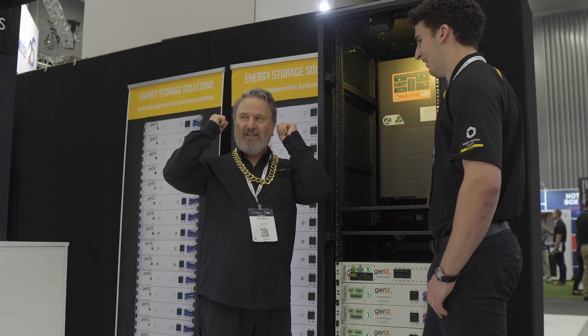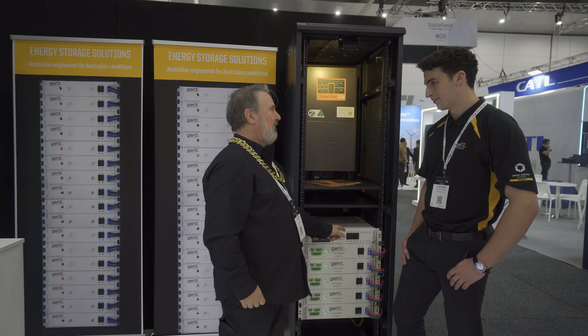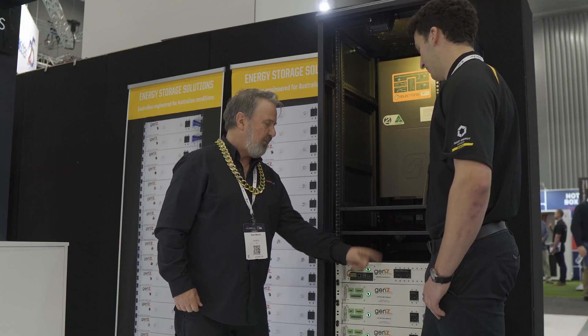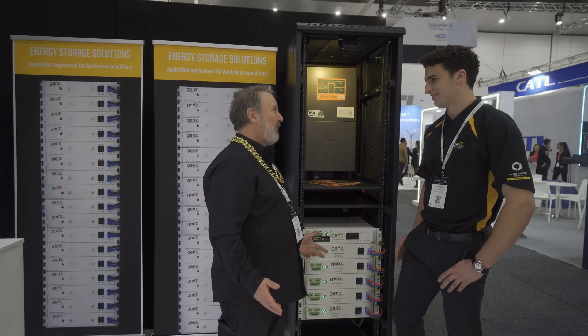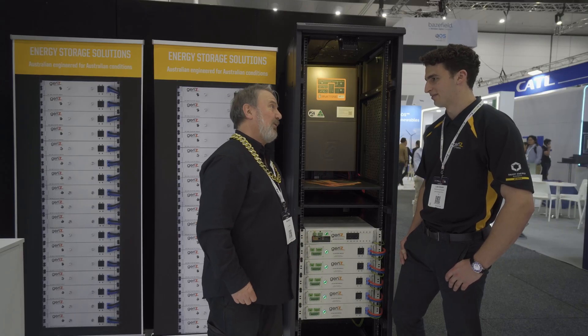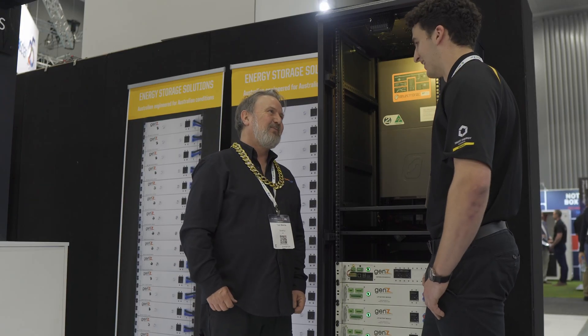I can put my AS/NZS 5139 hat on here. So this is lockable in the off position? These ones are not lockable. Can't you put a lockout dog on it? Yes, that's easy. You just solved the problem — a lockout dog is easy. Are they marked on and off? They do have on and off labeled on the front. Are they load breaking? They are load breaking indeed.